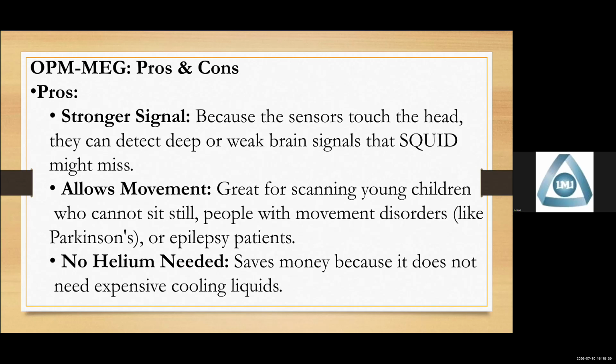Because the sensors touch the head, they can detect deep or weak brain signals that SQUID misses. It allows movement, which is great for scanning young children who cannot sit still, and people with movement disorders like Parkinson's or epilepsy patients. It's nice for these patients. No helium is needed, which saves money because it doesn't need expensive cooling liquid.